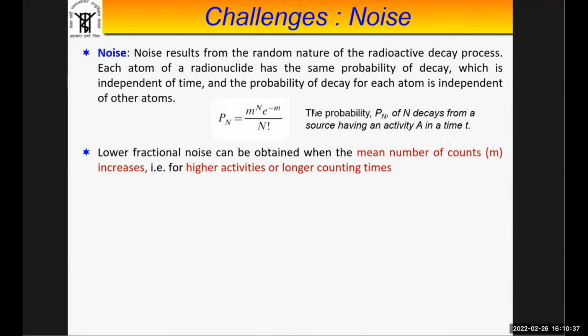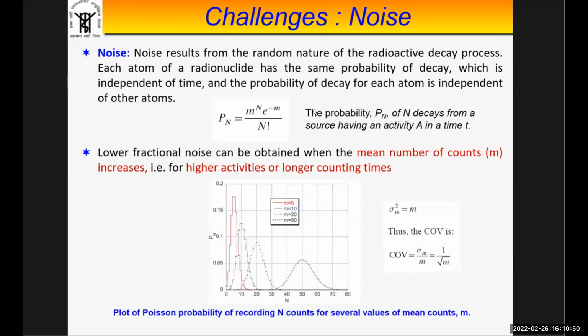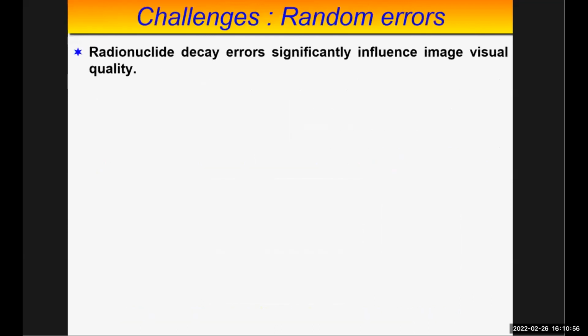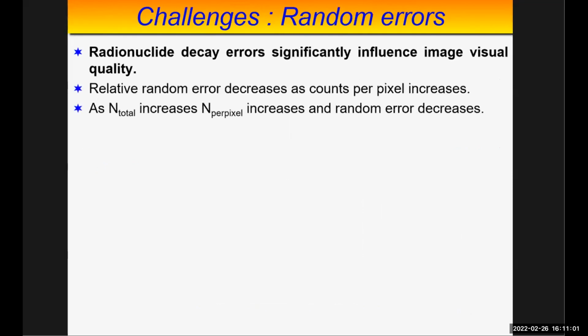Noise results from the random nature of the radioactive decay process. Each atom of a radionuclide has the same probability of decay, which is independent of time, and the probability of decay for each atom is independent of other atoms. Lower fractional noise can be obtained by increasing the number of counts or by using a longer counting time. Radionuclide decay error significantly influences the visual image quality.